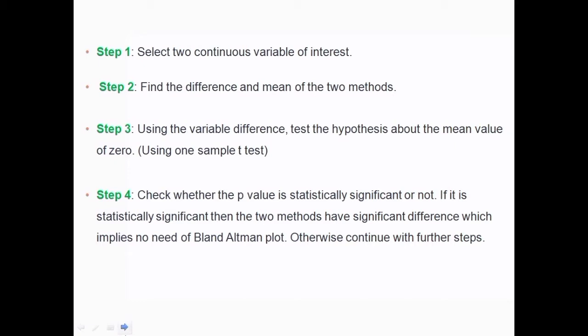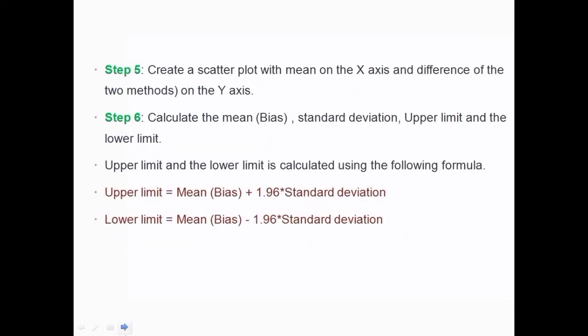Why do we need a non-significant p-value? Because we are testing that the difference should be almost zero — that there is no difference between the two methods. Our null hypothesis is: there is no difference. The alternative hypothesis is: there is a difference. So if we get a significant p-value, there is a difference between the methods. Only when we get a non-significant result can we say there is no difference. Step five: create a scatter plot with the mean on the x-axis and the difference on the y-axis.